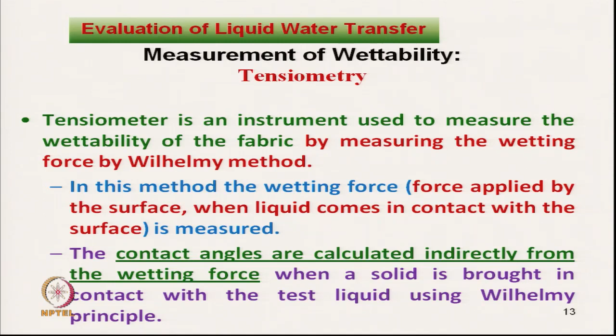Now, in this picture, the solid is, say, a glass plate. The Wilhelmy plate consists of a thin glass plate. The plate is often made from glass which may be roughened to ensure complete wetting. Complete wetting is required. The plate is cleaned thoroughly, otherwise if it contains some impurity, it will affect the wetting characteristics, and it is attached to a scale or balance via a thin wire. So, this is a thin wire, and with this it is attached to some tension measurement system. The force on the plate due to wetting is measured via a tensiometer or a microbalance, which is a force measurement system, and used to calculate the surface tension gamma using the Wilhelmy principle.